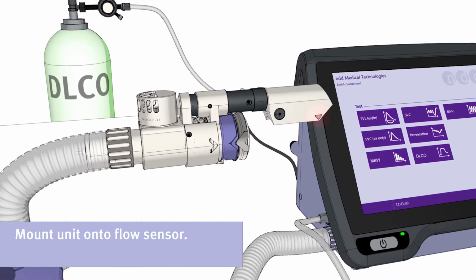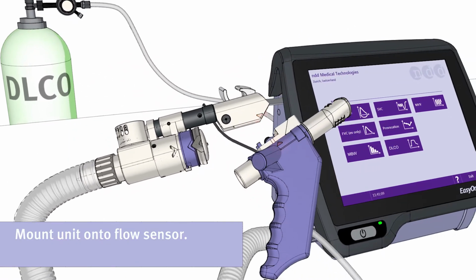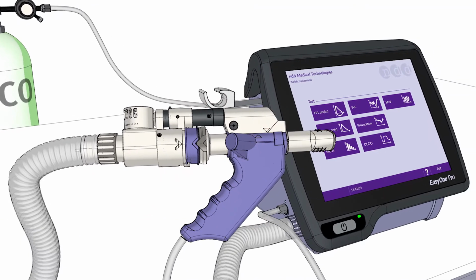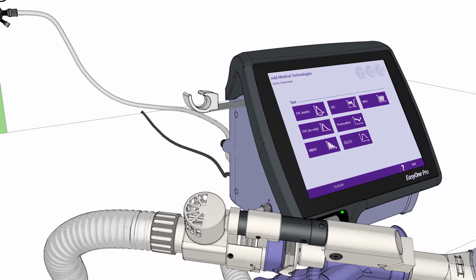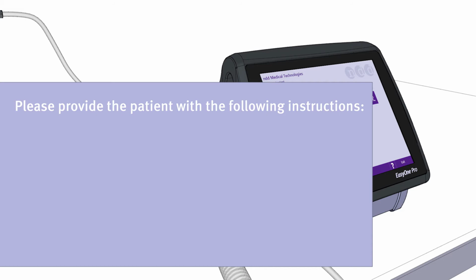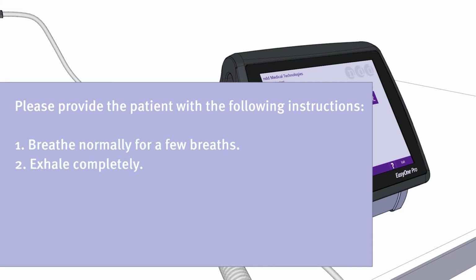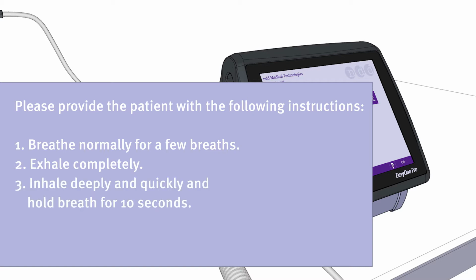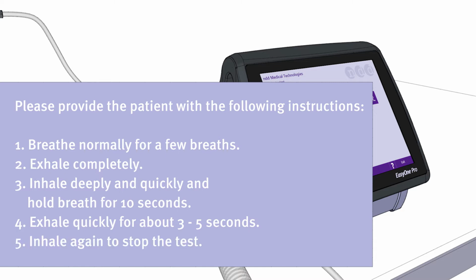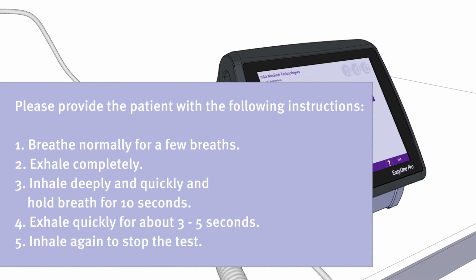And mount the unit onto the flow sensor. Please instruct the patient to breathe normally for a few breaths, then to exhale completely, then to inhale deeply and quickly and to hold the breath for 10 seconds, then to exhale quickly for about 3 to 5 seconds, and to inhale again to stop the test.